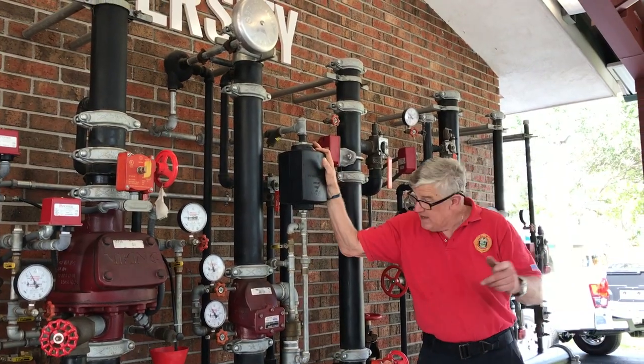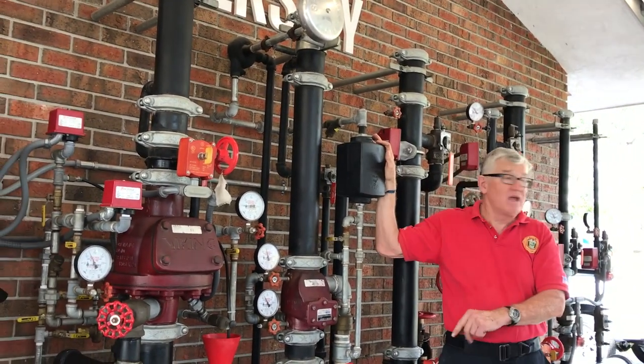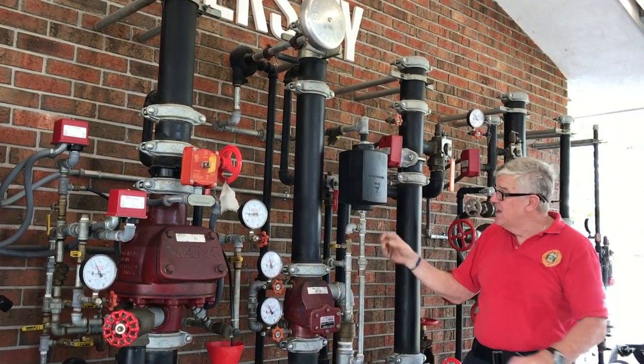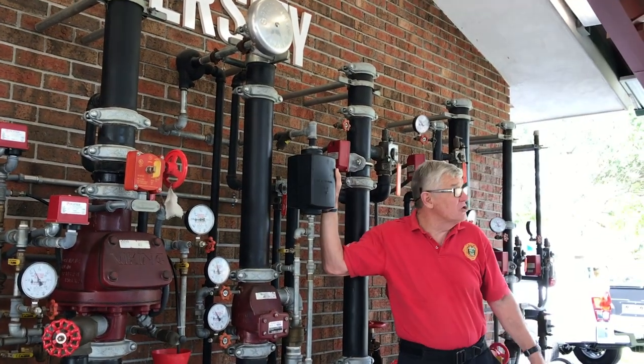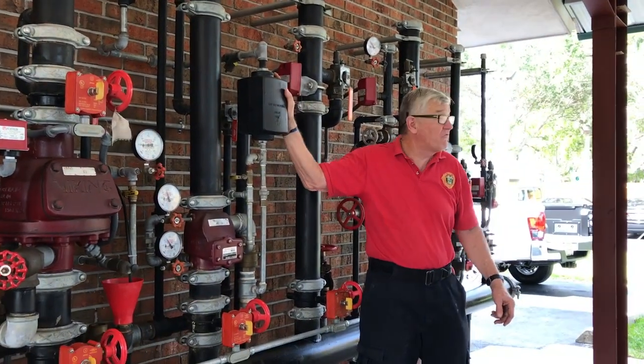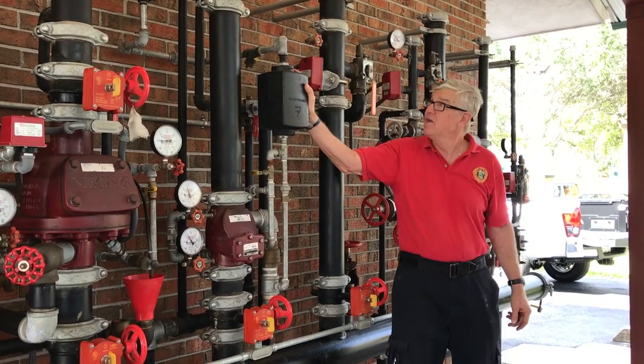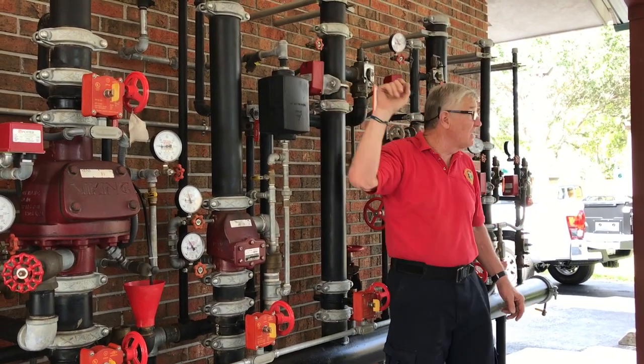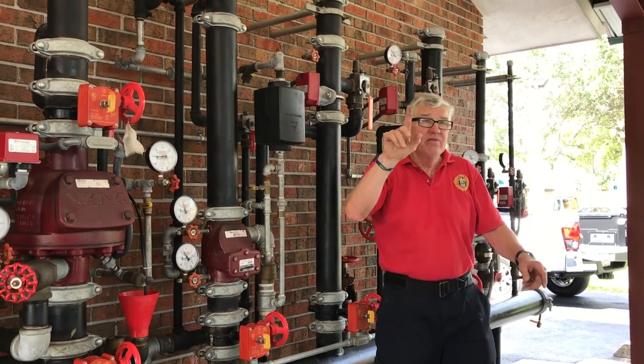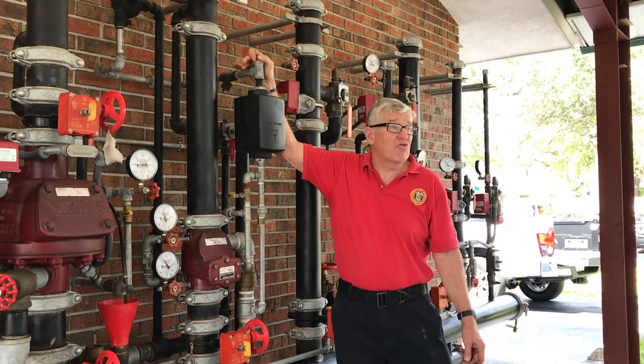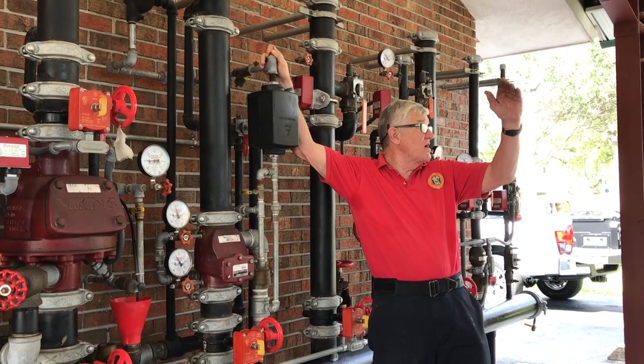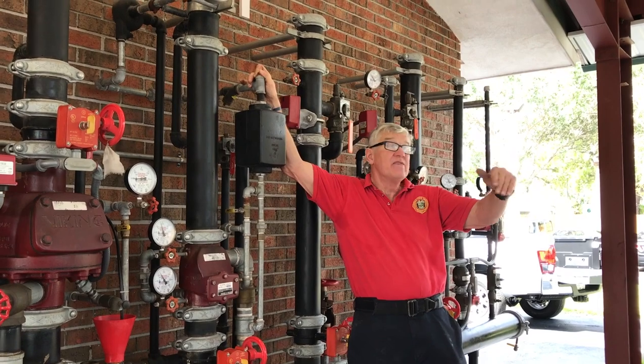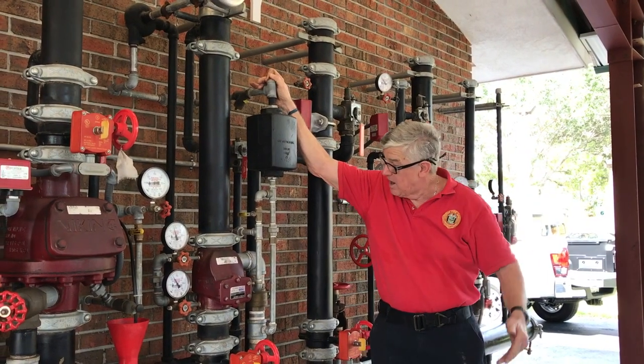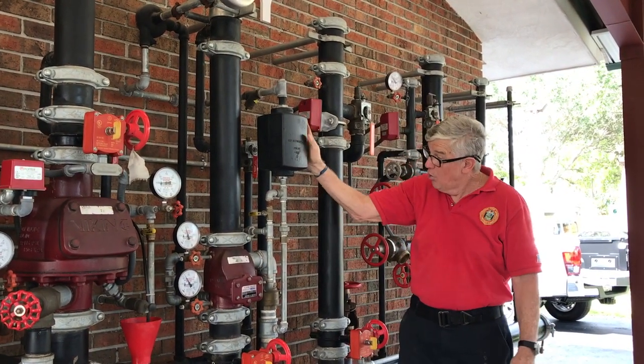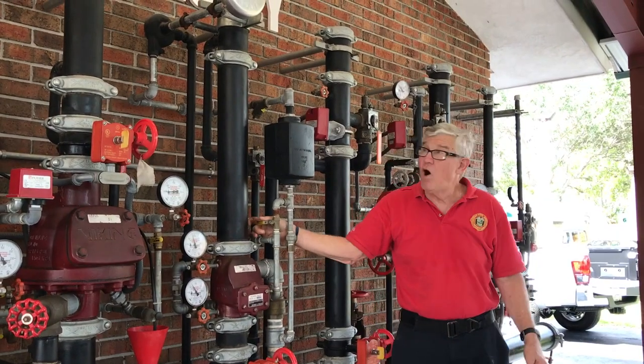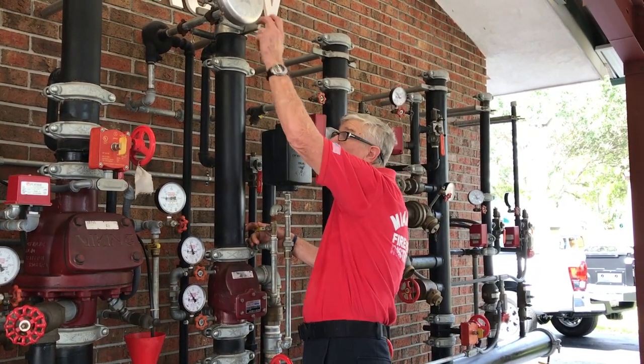Here, there is a drain in this retard chamber. If the retard chamber can drain faster than it fills due to a surge, we will not activate the water motor gong. Most of these systems have been retrofitted here with a pressure sensitive electric switch that will initiate a water flow alarm. Here, we're going to test the water motor gong old school.